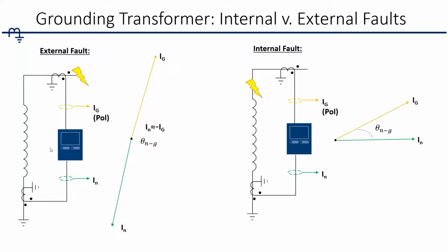So here's kind of what you're going to see. If you placed a fault external to the grounding transformer, and you grabbed the data from the relay itself and compared the angle difference between the ground and neutral measurement, so your CT here, summing at the top, and then your bottom measurement here, if you measure this angle, it's roughly 180 degrees. There's going to be a little bit of difference there just from measurement error and other things, but you're going to see a large angle here for external faults.